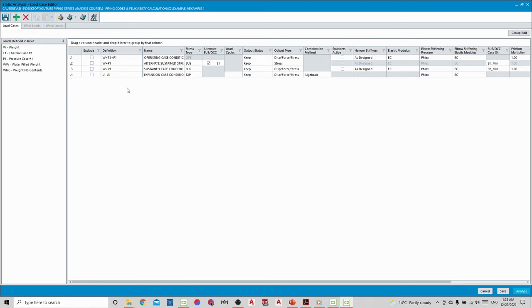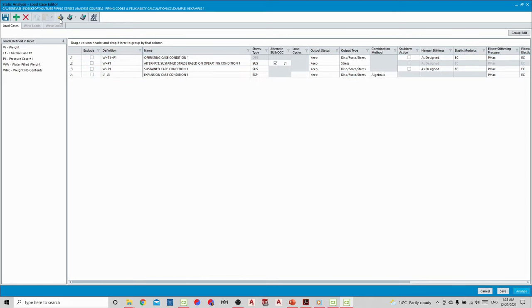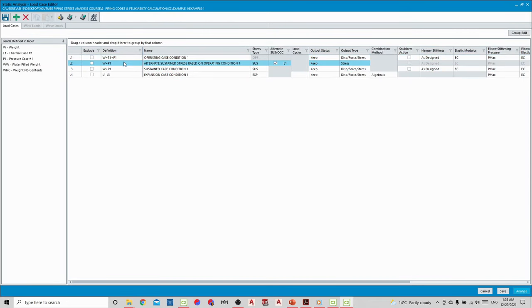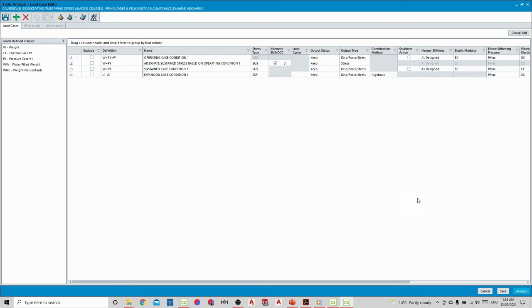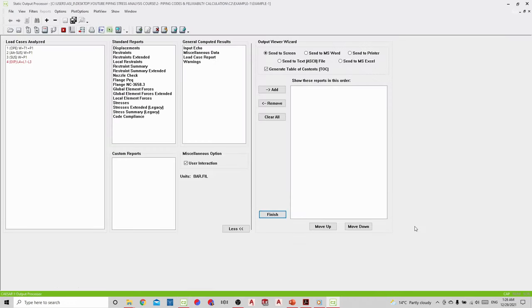This is the load case table based on the code. The only thing not mentioned is the occasional load, but the code provides that option. These are the main requested load cases — you can use them from here. This is the operating case, and this is the alternative sustained. I will explain every load case and why we use the sustained and expansion load cases. Press Analysis and we go back to the analysis.